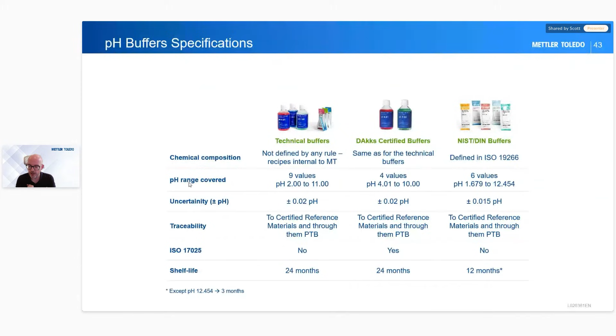When we do a calibration, we've taken our system, we've stored the electrode correctly, we've made sure it's clean and ready to go, and we've taken a calibration, an offset, an adjustment. Here's what's happening: we've done a sensor calibration, and it goes back through this offset and calibration slope. Here you can see the designation that at Mettler Toledo we decide is a good or a bad calibration. If it's between plus or minus 5% and 0 to 20 millivolts, we say everything's good. In our meters, you will see a little symbol that looks like a telephone signal with 3 bars, and these 3 bars actually show this type of thing.